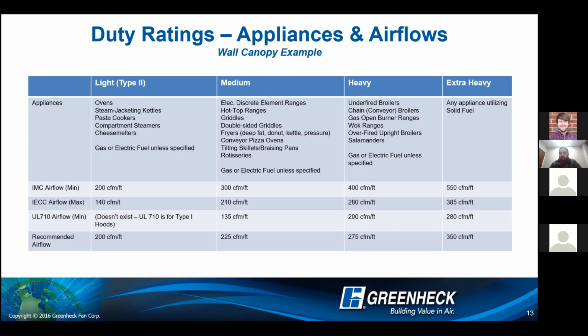That same section also calls out that any UL listed hood does not have to follow the IMC minimums, which is a good thing, because let's say we had a 10-foot hood, IMC would say we need to have a minimum of 4,000 CFM. Now, the next thing I'll call your attention to is UL 710 airflow minimums. So because we have a UL listing, we have minimum CFMs that these hoods can be sized to.